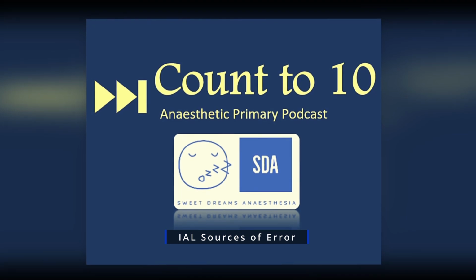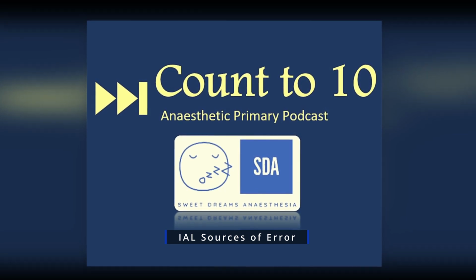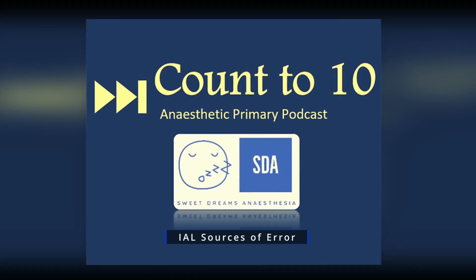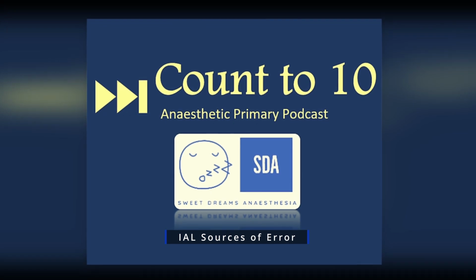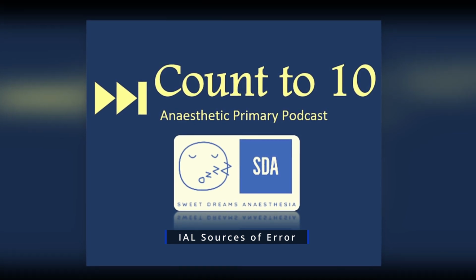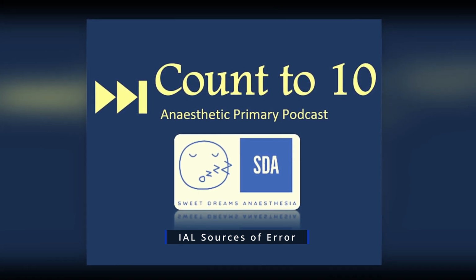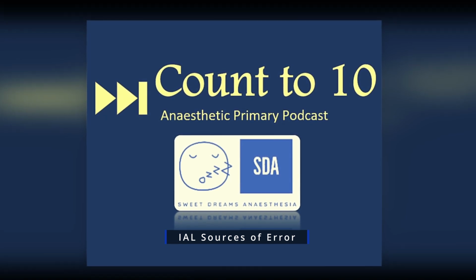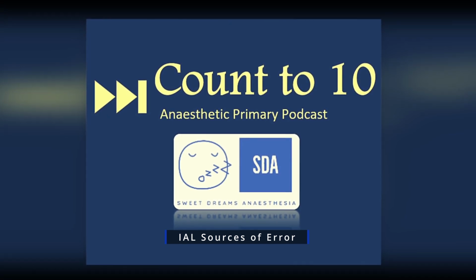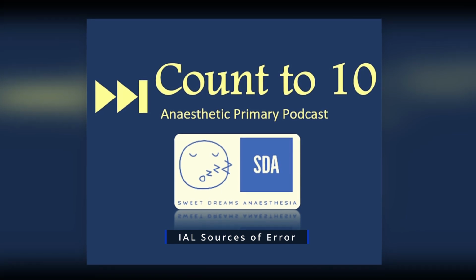Why do we care so much about resonance and natural frequency? If the system's natural frequency is low, this can lead to an overestimation of systolic blood pressure and an underestimation of diastolic blood pressure. However, importantly, mean arterial pressure should remain accurate.